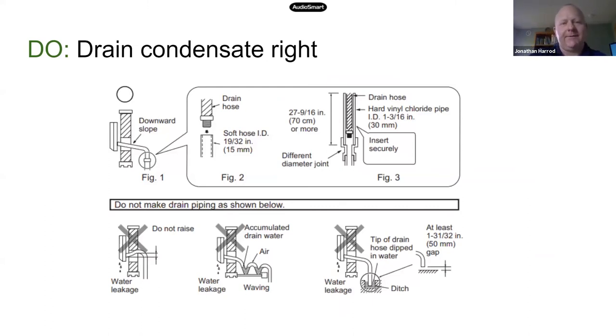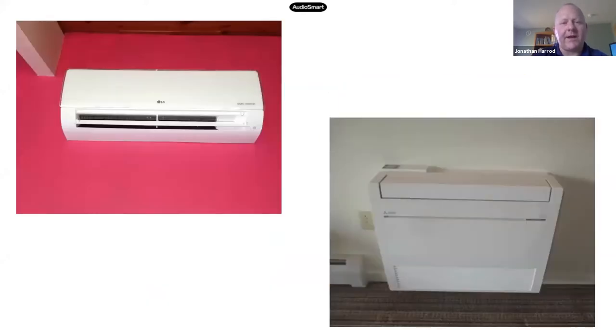Condensate. As we find that we're getting hotter and more humid summers, we're doing more air conditioning, and managing condensate, which is the moisture that's pulled out of our indoor air in air conditioning, becomes a really important consideration. Backing up to this high wall unit, and I talk a lot about high wall units because they're about 90% of what we install. So the air comes in the top, passes over the heat exchanger, there's a little fan, and it blows out through the louvers. As it passes over the heat exchanger, it's cooled and condensation happens. That condensation runs down to a little drain pan, and then that condensate drains by gravity out of the house and down to the ground. That's a pretty typical installation. It's 100% gravity drained.